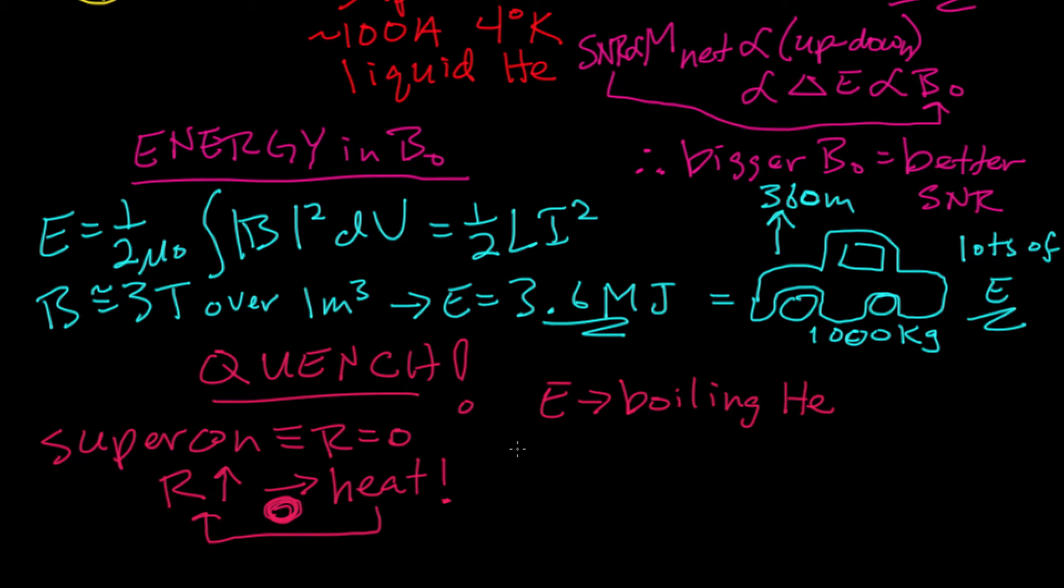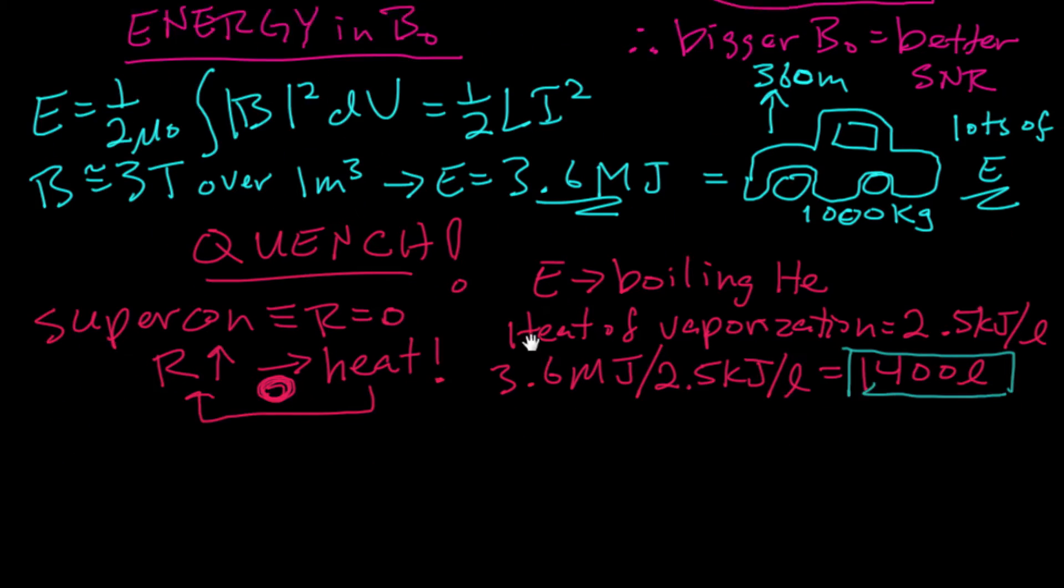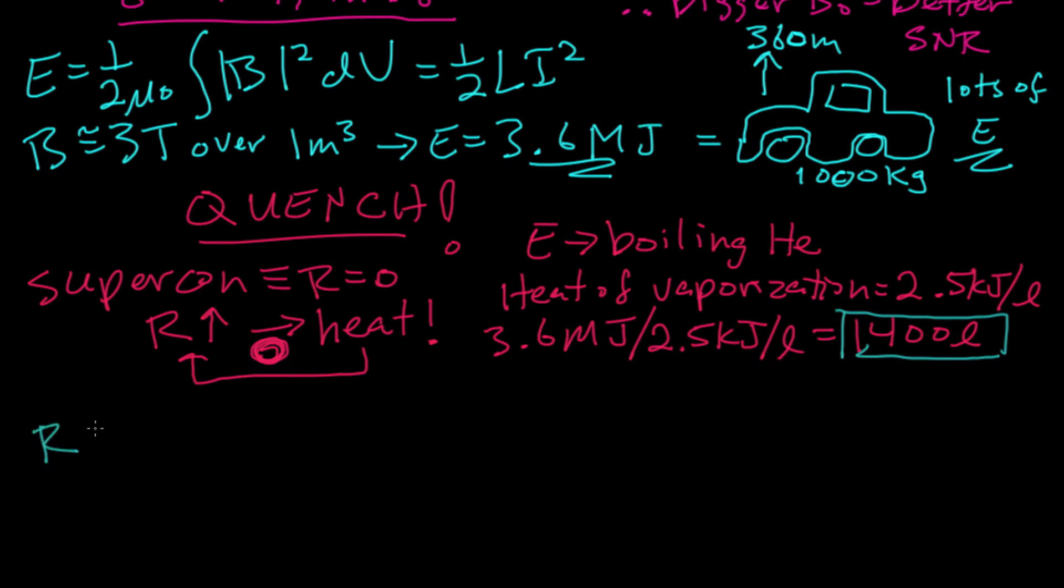The energy ends up going into the boiling of the liquid helium. The heat of vaporization of liquid helium is about 2.5 kilojoules per liter. If you do the math, that 3.6 megajoules of energy into 2.5 kilojoules per liter means that that amount of energy can boil off 1,400 liters of liquid helium. Not coincidentally, that's just about the amount of liquid helium that's in a 3T scanner.